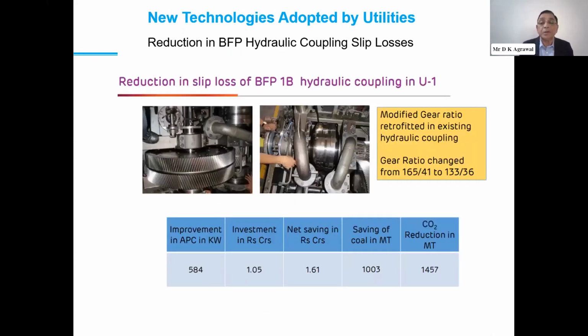This is just giving one example. There are cases in some of the utilities where there are high levels of slip losses in the boiler feed pumps, hydraulic coupling. In many places people have replaced these hydraulic coupling gears, and these slip losses have been reduced, and you can see in this table the type of savings which they are able to achieve. So I feel whichever type of units, particularly up to 300 megawatt units, because for 500 we have TDBFP and all. But it is quite beneficial, and you can have a good saving. Next slide.